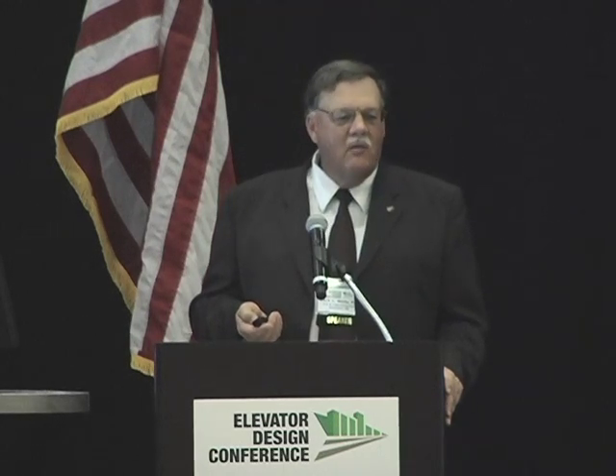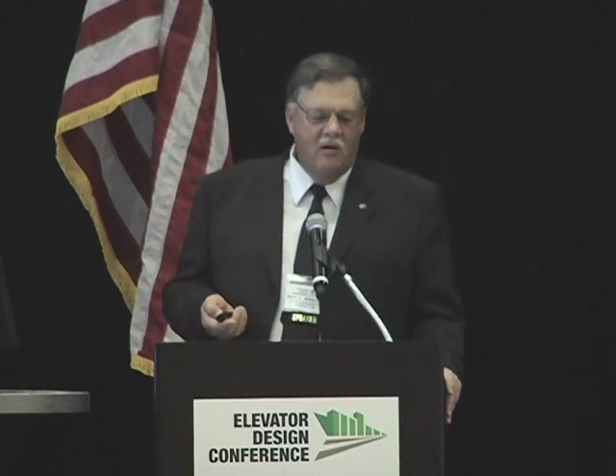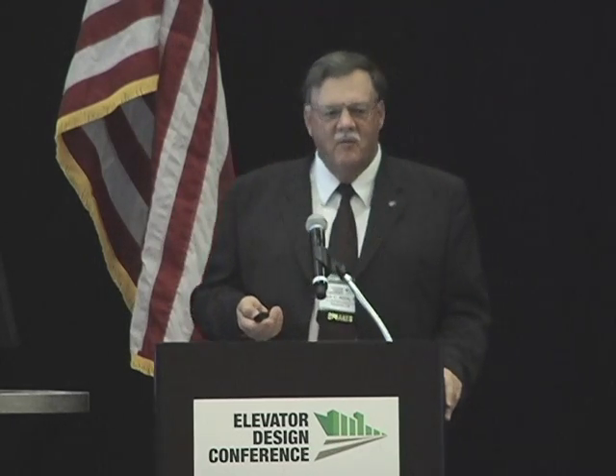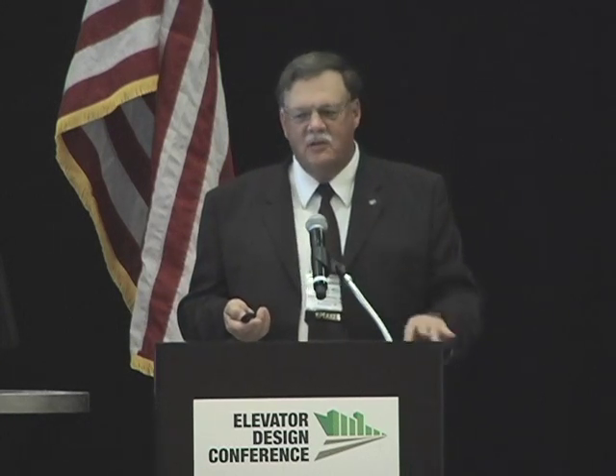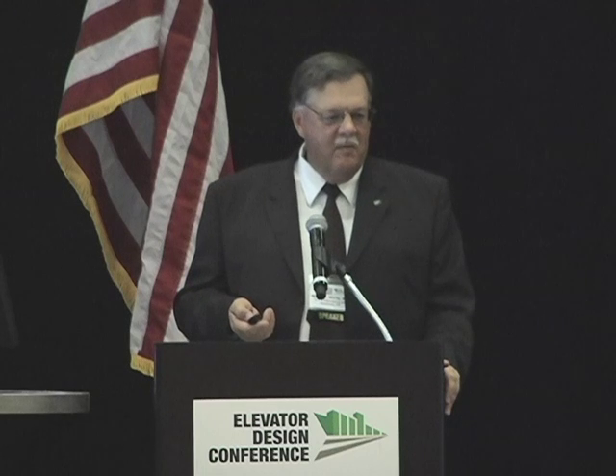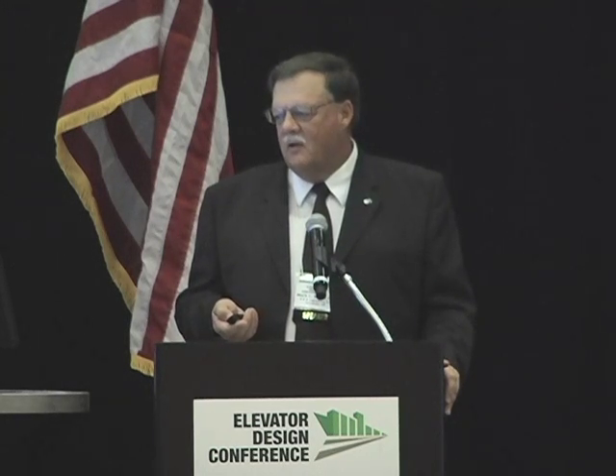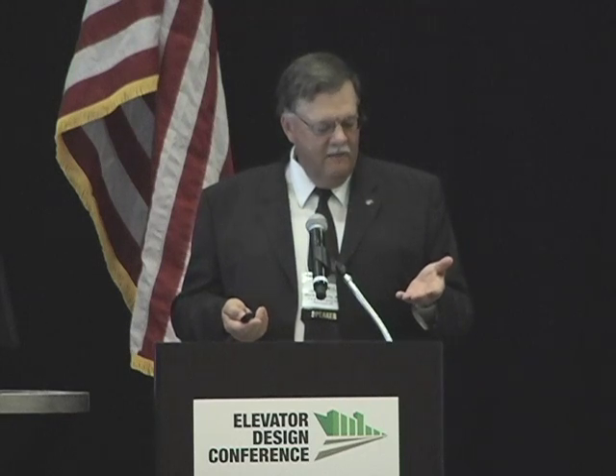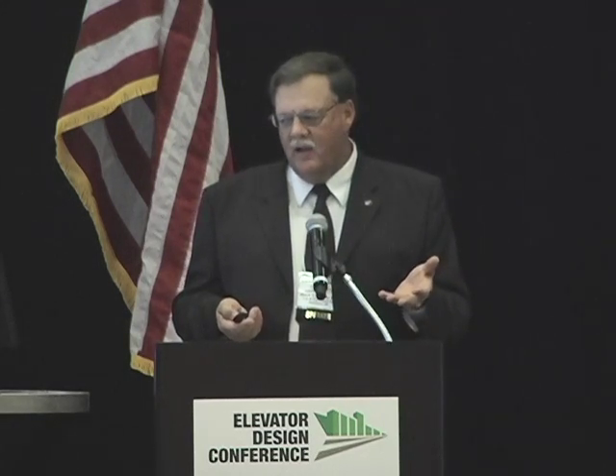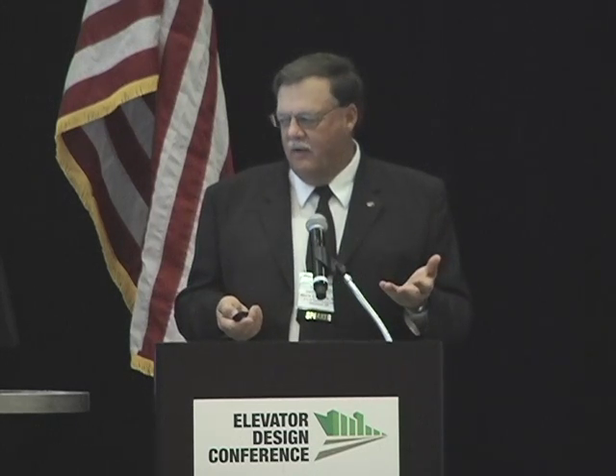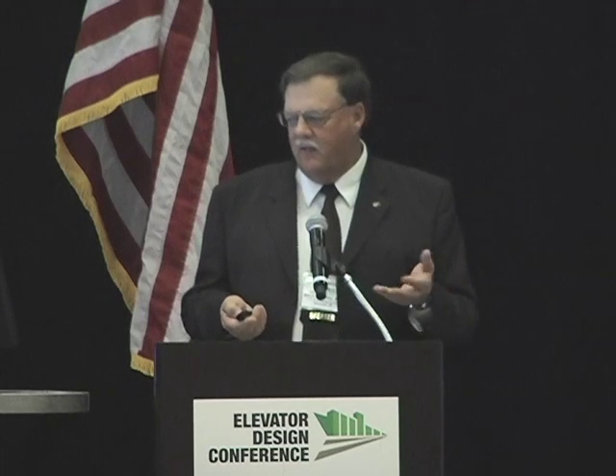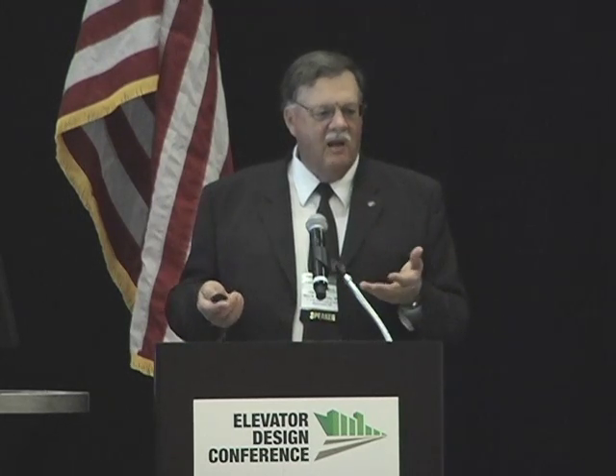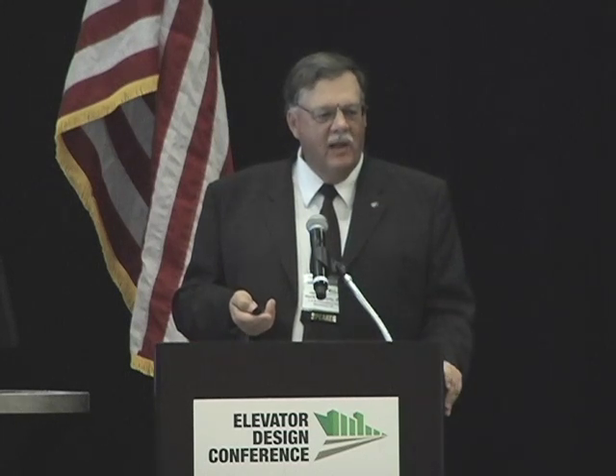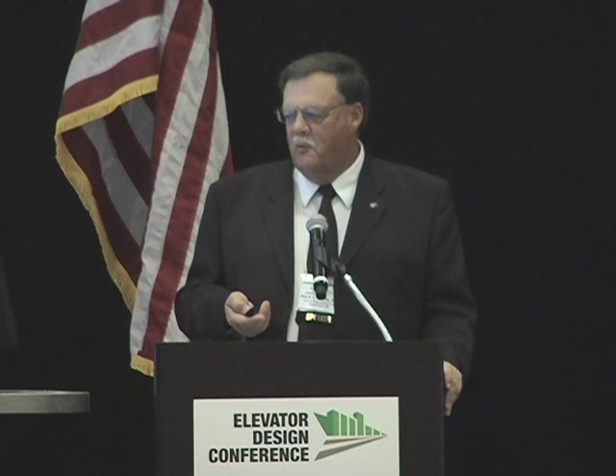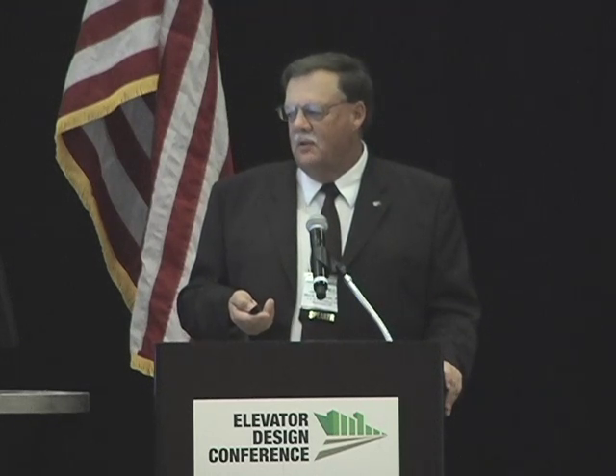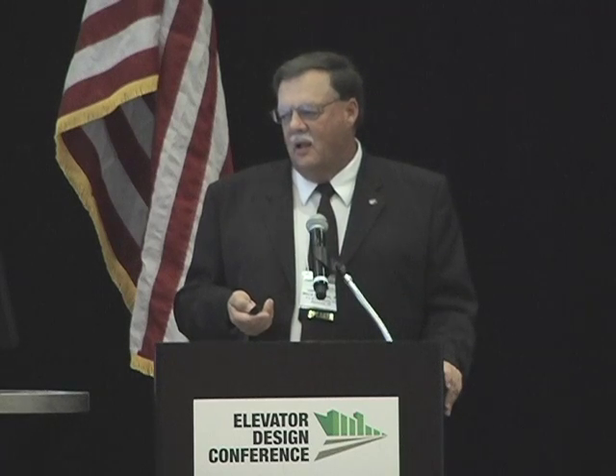Electronic motor overload systems. Almost all manufacturers now have a standard overload that is an electronic motor overload versus the old melting alloy heater elements and so forth. And they have a lot of capabilities. Some of them even have communications so that you can get down to an overload relay on an individual motor starter. In fact, the Siemens ones, I'll show you a picture here, some of them have auxiliary inputs on them. Like if you want to bring a motor winding temperature analog into the overload relay instead of into the control circuitry. They can do remote communications. They have jogging mode configurations and so forth.